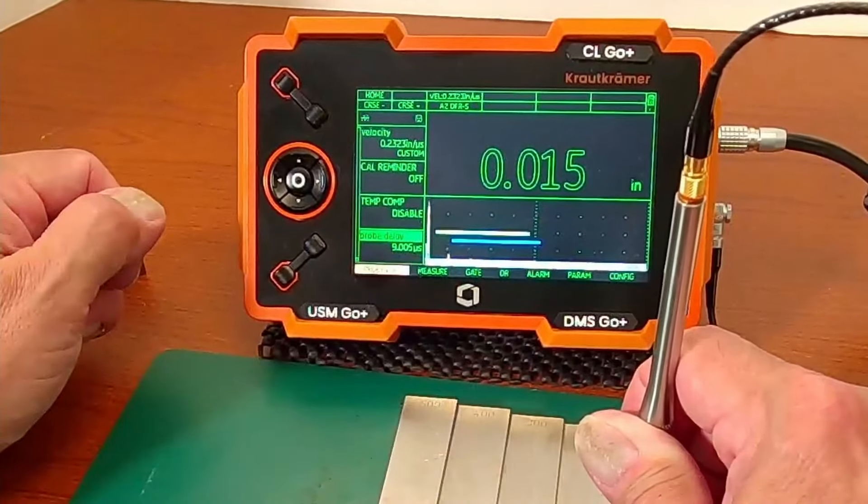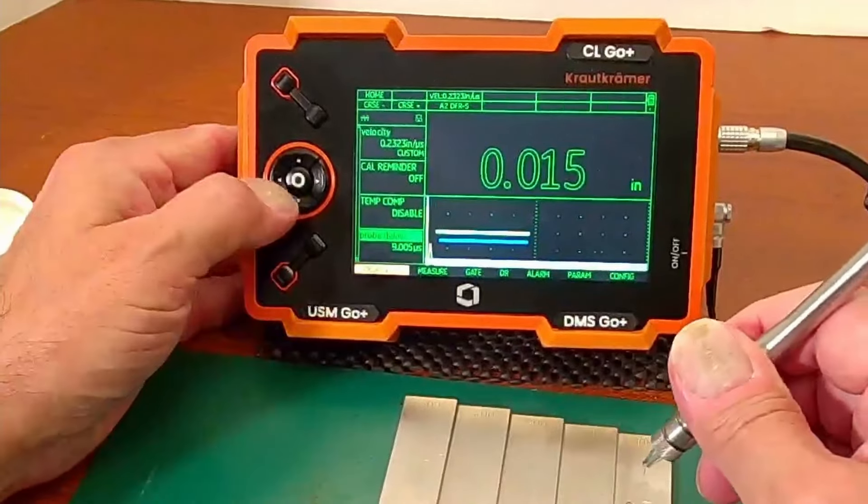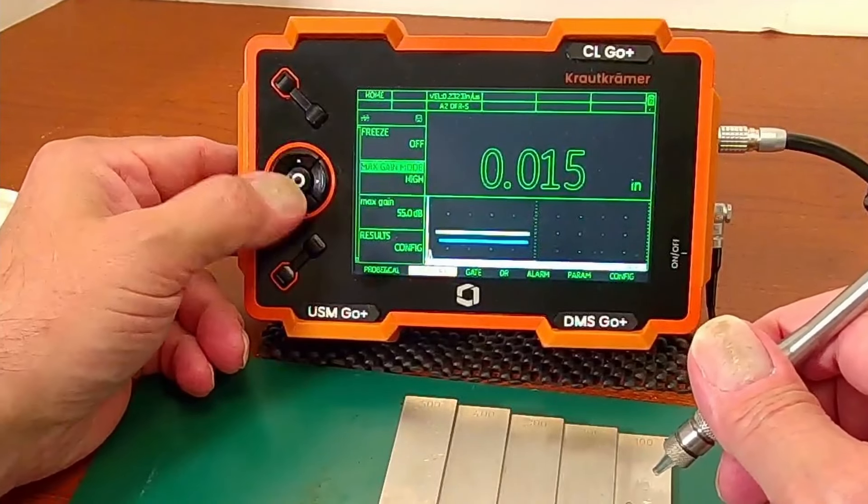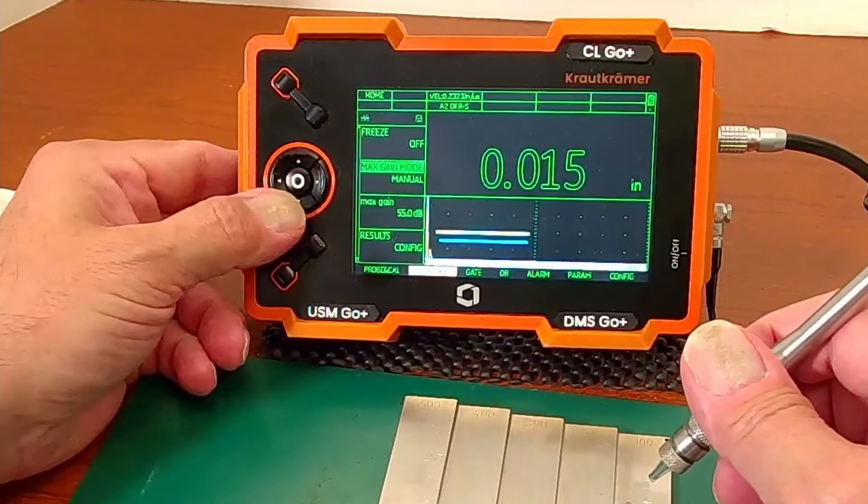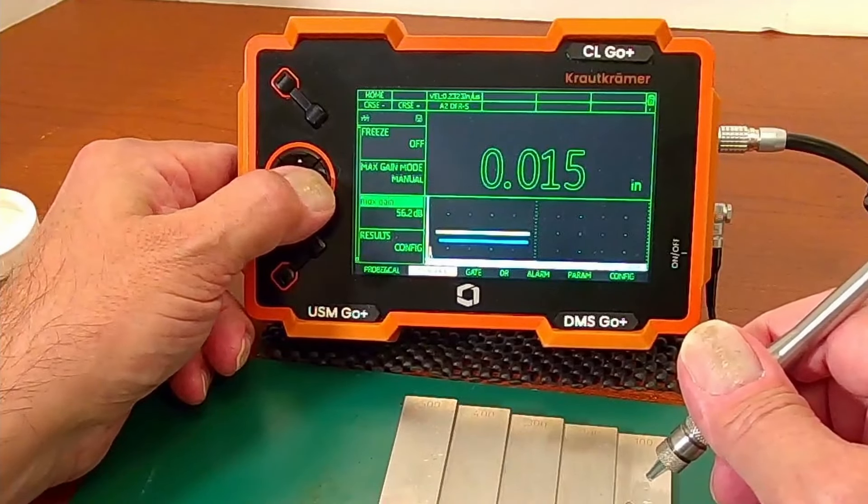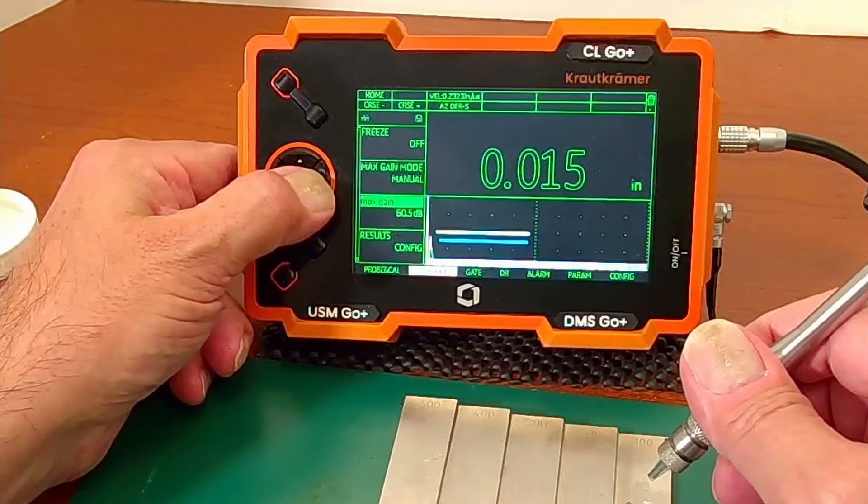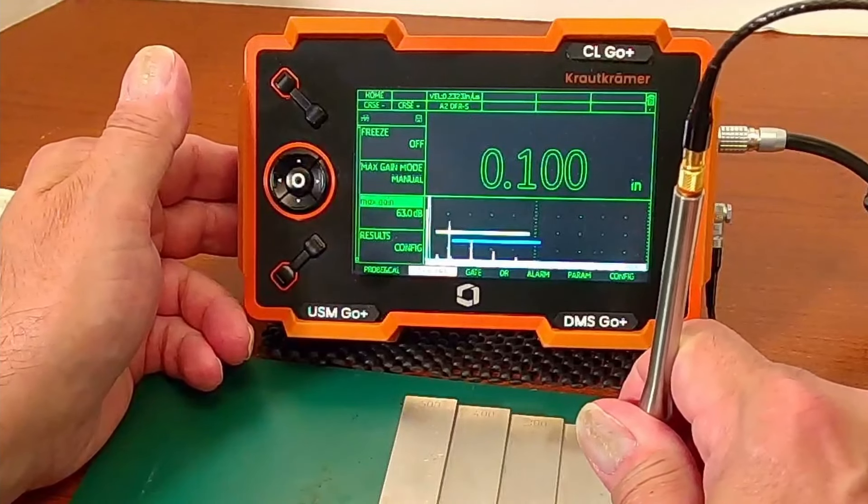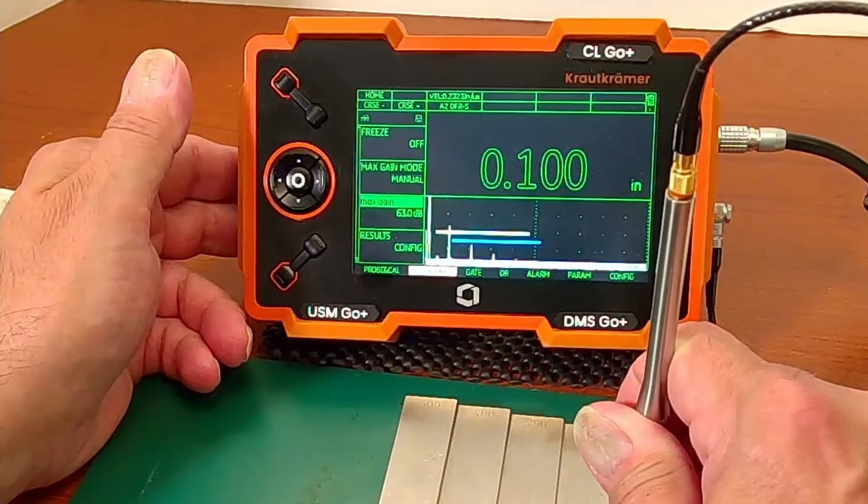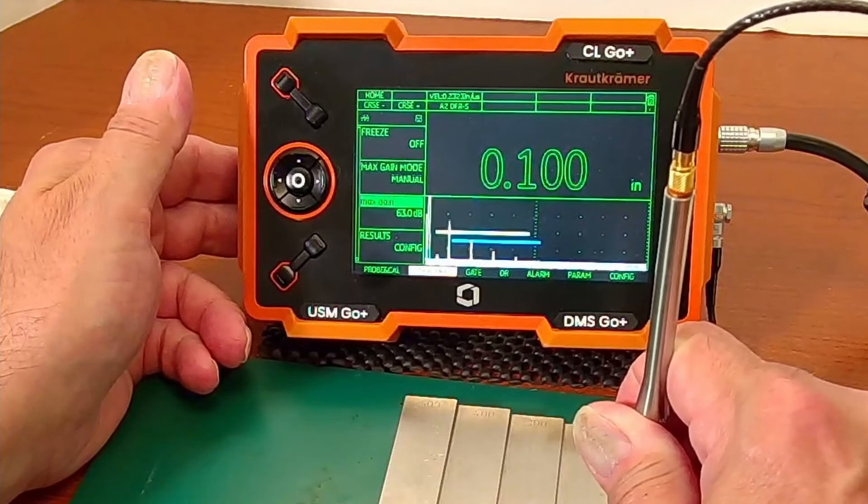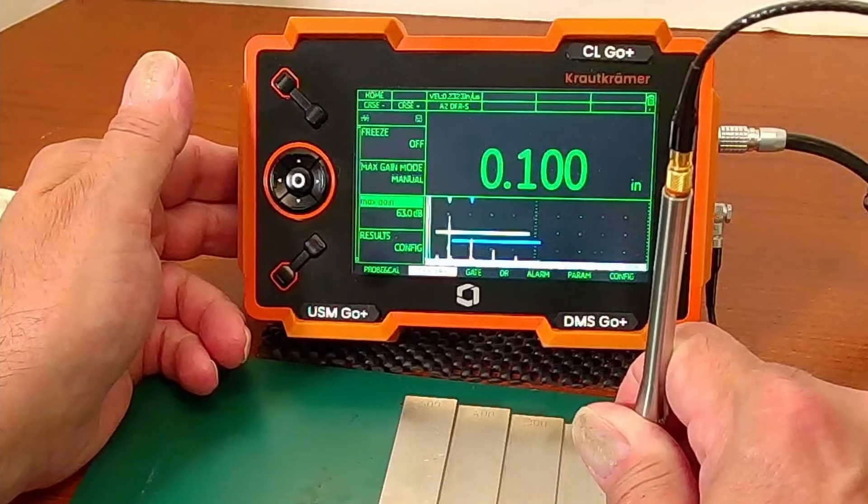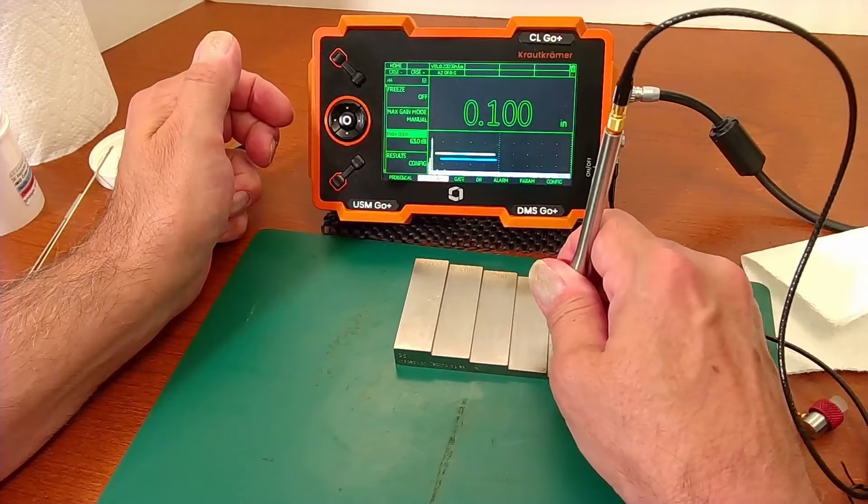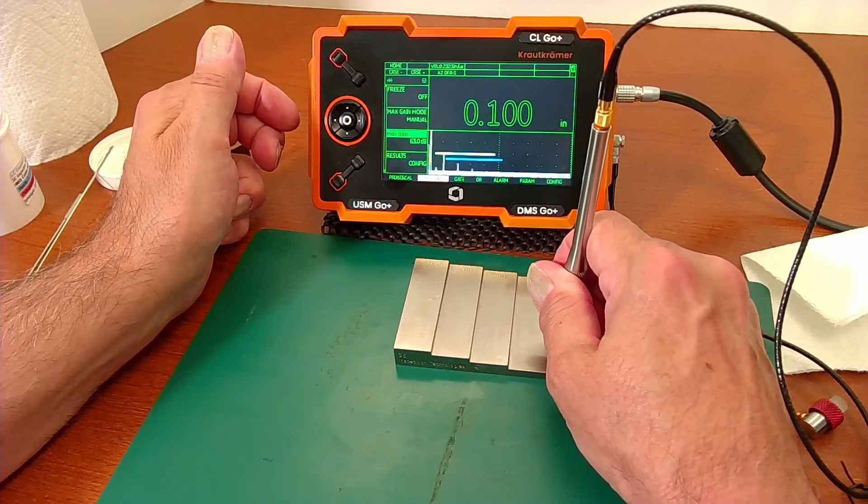So I can go into my measure menu, go up to the max gain mode, switch that to manual, and I'm going to increase my gain here to sort of mid 60s. Let's go to like 63 or so. Now you notice when I get the probe on, I get it squared up and the signals peaked up, now I'm breaking the gates and I'm getting readings. Now it is still trying to do automatic gain control, so it's adjusting the gain even after I've peaked up the probe.